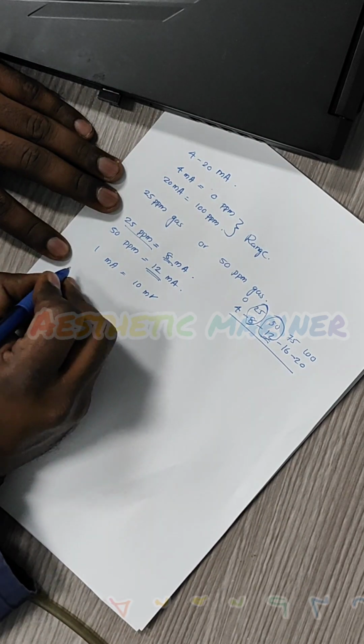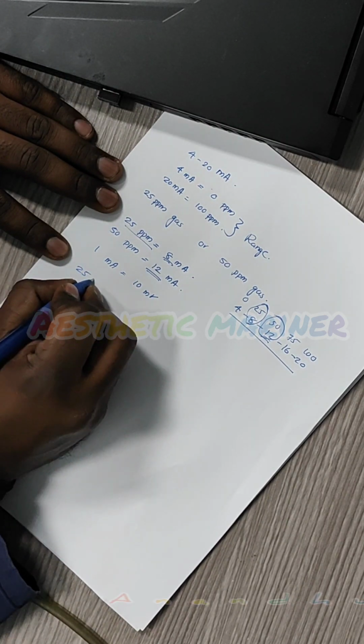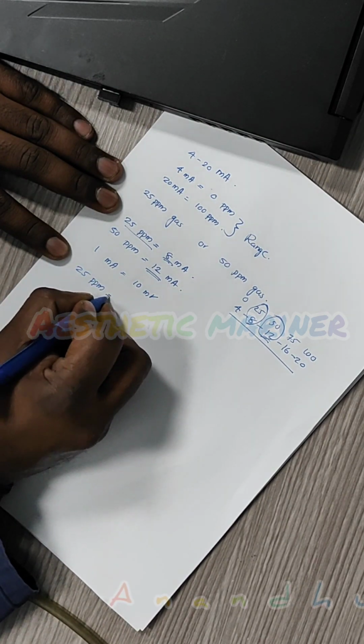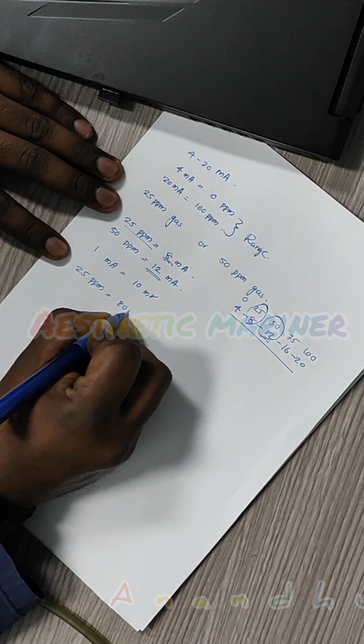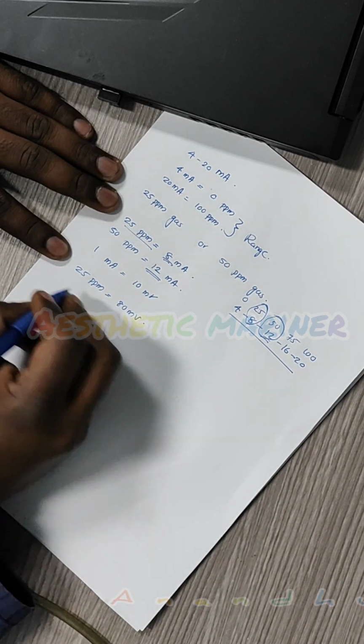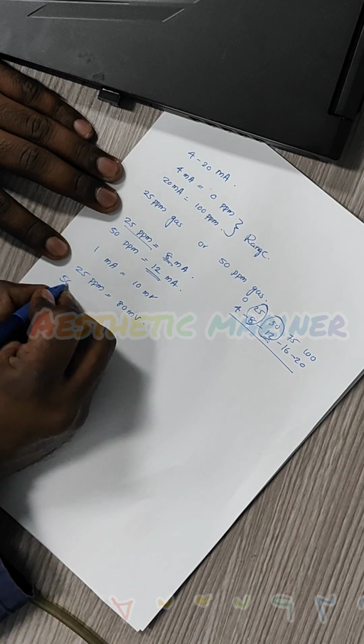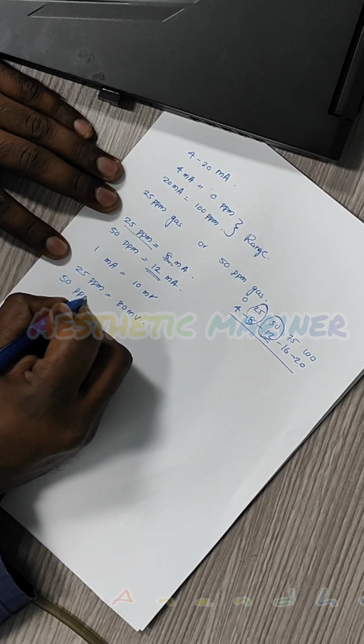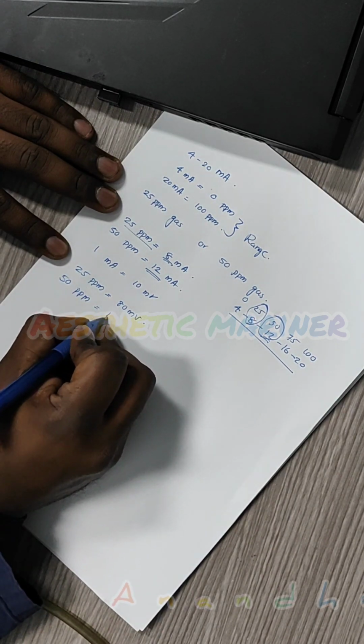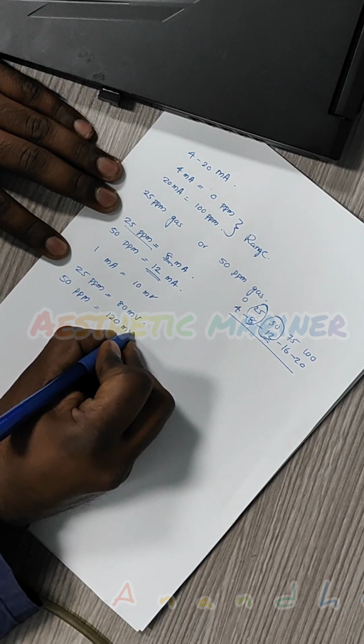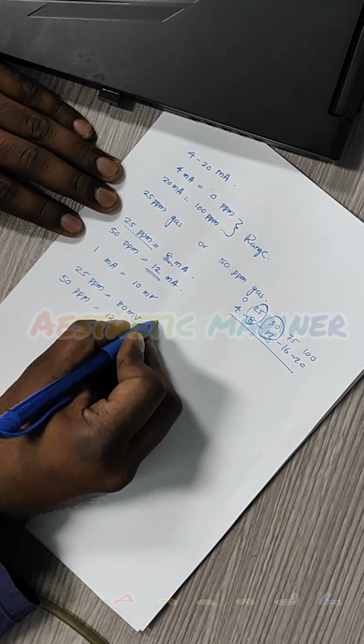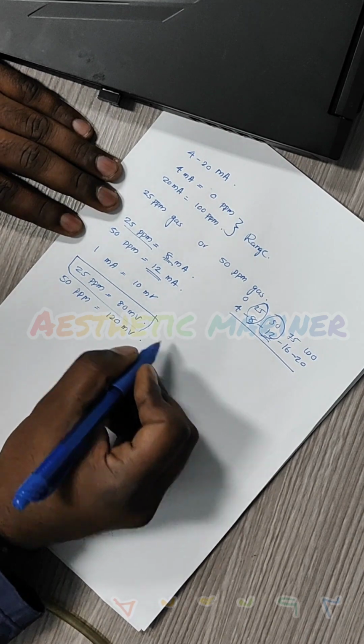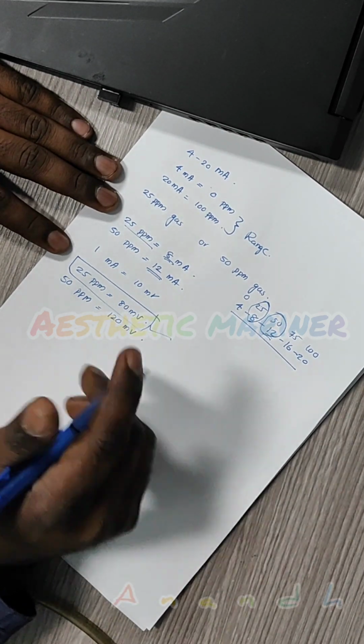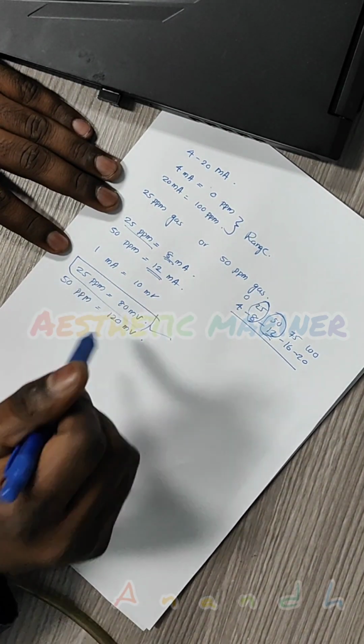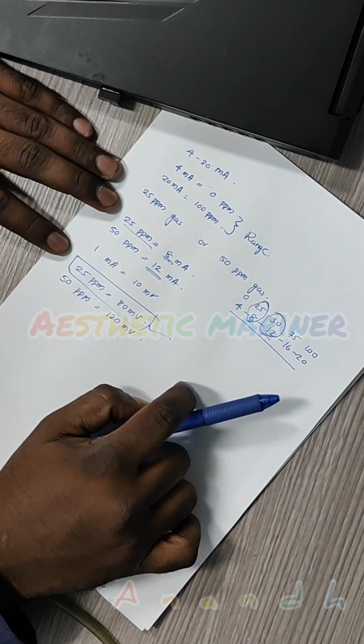Now if I am doing 25 ppm gas, I need 80 millivolt. If I am doing 50 ppm gas, it equals 120 millivolt. So I am choosing 25 here, and we will do the calibration with 25. For the calibration, we just need to be aware of this millivolt conversion.